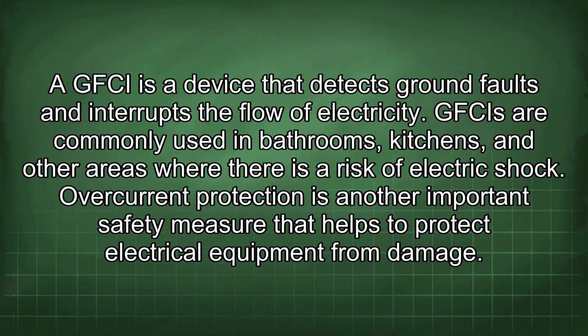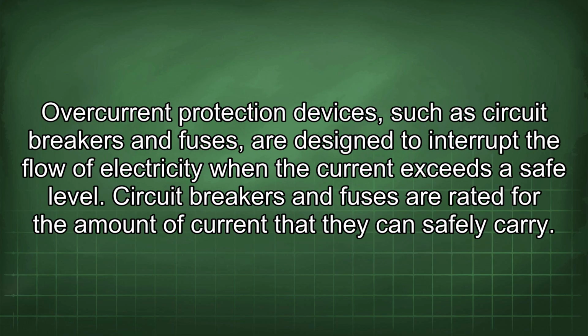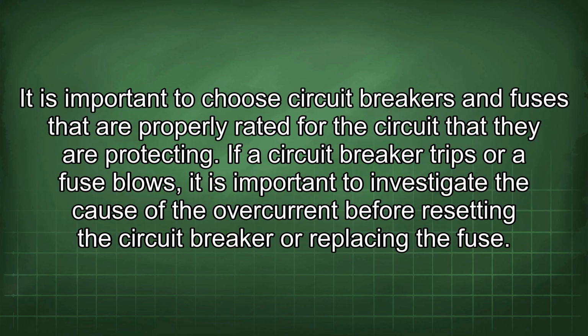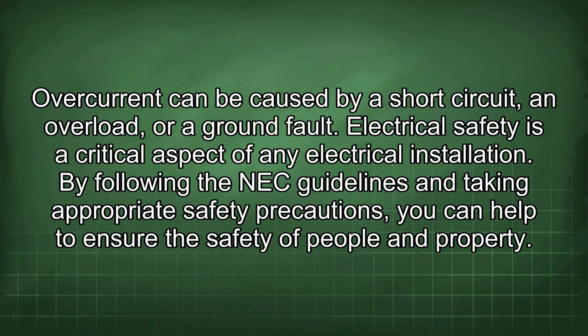Overcurrent protection is another important safety measure that helps to protect electrical equipment from damage. Overcurrent protection devices, such as circuit breakers and fuses, are designed to interrupt the flow of electricity when the current exceeds a safe level. Circuit breakers and fuses are rated for the amount of current that they can safely carry. It is important to choose circuit breakers and fuses that are properly rated for the circuit that they are protecting. If a circuit breaker trips or a fuse blows, it is important to investigate the cause of the overcurrent before resetting the circuit breaker or replacing the fuse. Overcurrent can be caused by a short circuit, an overload, or a ground fault.